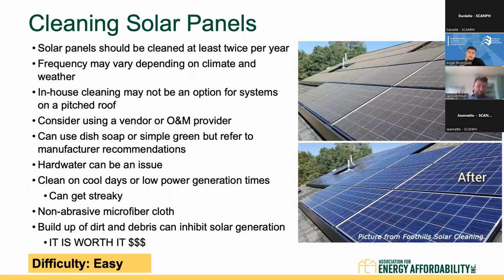Besides monitoring and visual inspections, this is an additional thing you need to be considerate of when maintaining solar PV systems. Solar panels should be cleaned at least twice per year. Oftentimes you'll hear solar manufacturers say that you don't need to clean them because it's going to rain and the rain will clean them. However, what we've experienced from our projects is that solar panels often need to be cleaned, and by cleaning the panels you are going to see quite a large boost in kilowatt hour generation from those panels. The frequency of cleaning may vary depending on climate and weather. If you have less rain, you're probably going to have to clean them more frequently. If you live in a dusty climate, you're probably going to have to clean them more frequently.